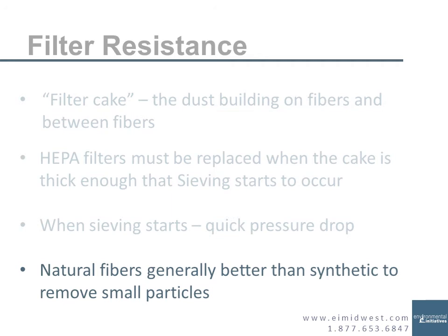And now one thing to think about, and this might sound a little strange at first, but natural fiber filters are better than synthetic fibers, and they're going to actually clog faster too, because they're simply removing more particles more quickly. Natural fibers are thinner in general than synthetic fibers. So synthetic fibers are wider fibers. A thinner fiber means the airflow that's going around that fiber has less curve. So basically more particles, because they're being forced to curve less, are running into the fibers themselves.